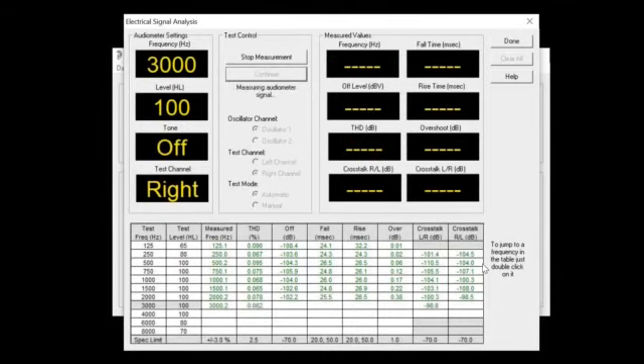So this is what I'm saying. The computer has full control. It doesn't get tired. It doesn't get bored. It doesn't get late for an appointment. It just does the calibration of your audiometer exactly the way the manufacturer's specification and ANSI certification says it's supposed to be done. There are no shortcuts. There's no okays. There's no lines through a linearity. There's no close enough attitude.